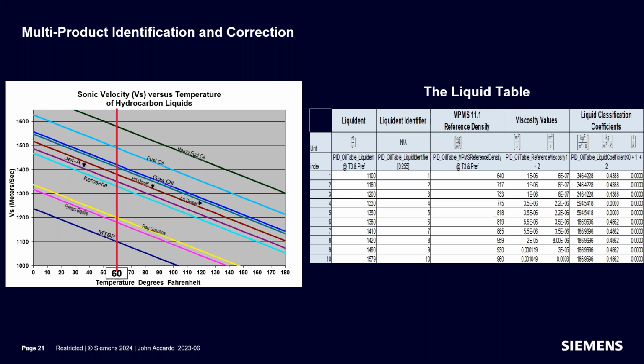What you might notice from the chart on the left is that as temperature goes up, the speed of sound of each of these products gets lower. It goes down. But they all follow exactly the same slope. Thank goodness, because otherwise we wouldn't be able to do this. So they all change at a rate of 2.3 meters per second for every 1 degree Fahrenheit, or 4.1 meters per second for every 1 degree Celsius.